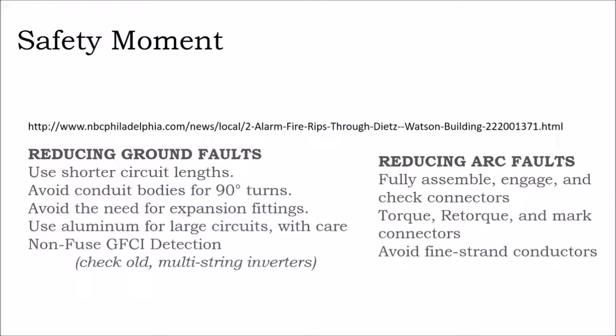To reduce ground faults, avoid anywhere your circuits can be dragging across a hard surface or against a surface that has a jagged edge on it, such as where a conductor meets, or a conduit meets another conduit. Expansion fittings that don't work can cause a problem. If you keep your array subsections small enough that thermal coefficient of expansion is no longer necessary, then you get less of a need for expansion fittings.